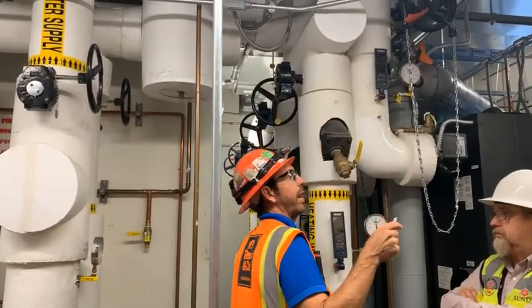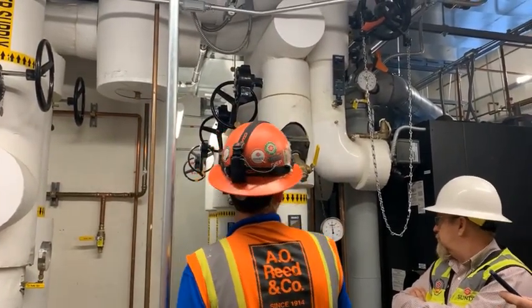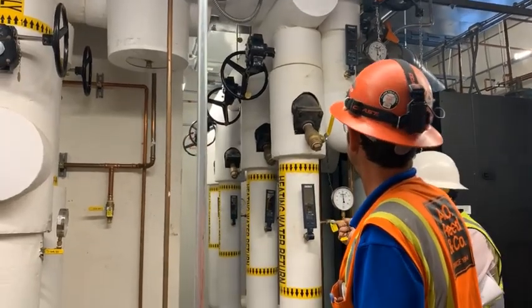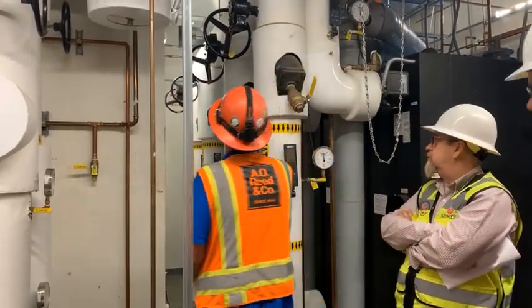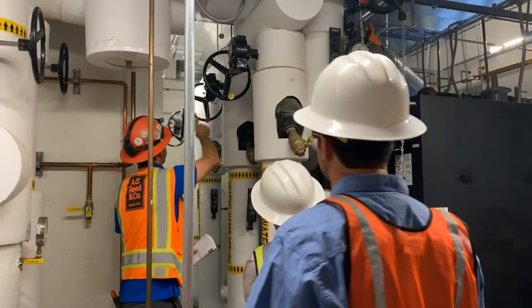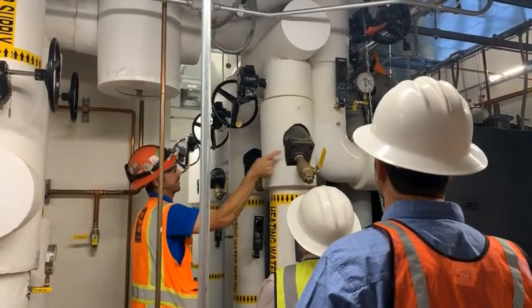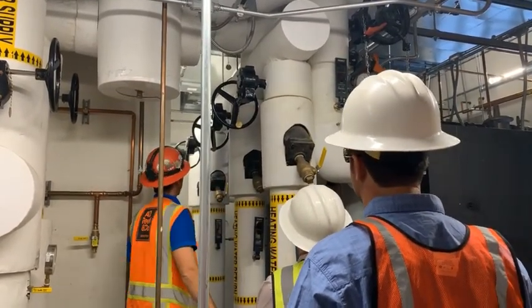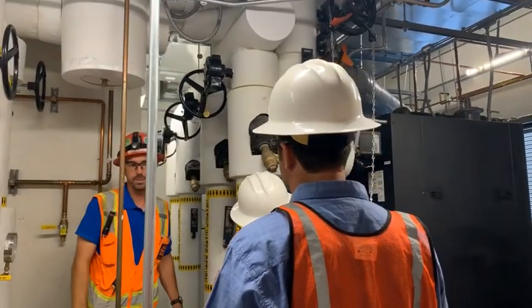We'll keep moving on out of this room here. We got our 4 boilers. These are our heating hot water boilers. We do have shut-off valves on the inlets and the outlets of every boiler, and every boiler has a strainer, okay? All the strainers were cleaned during our flushing procedure.